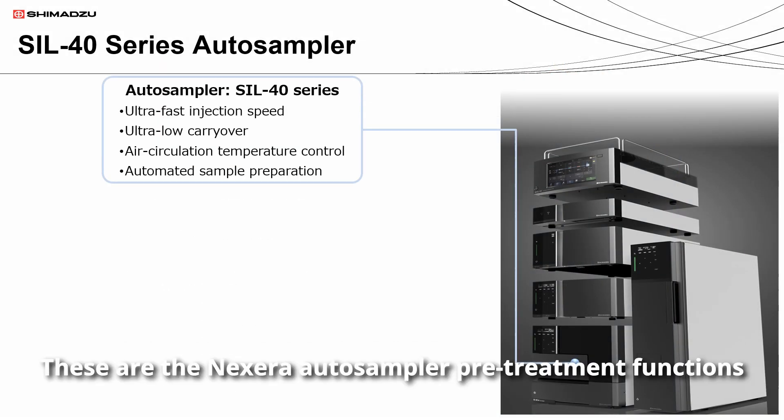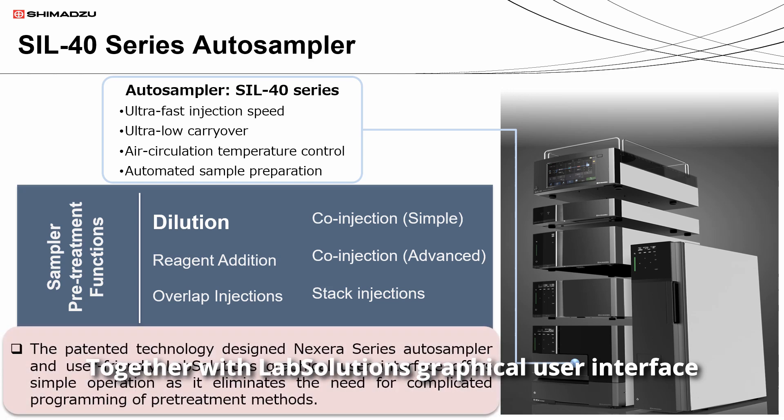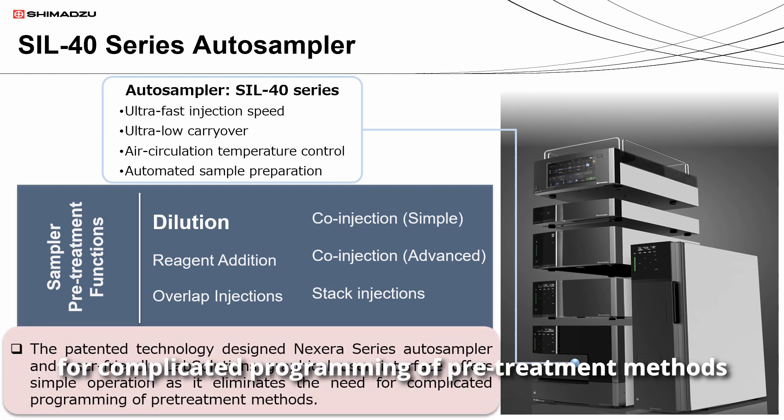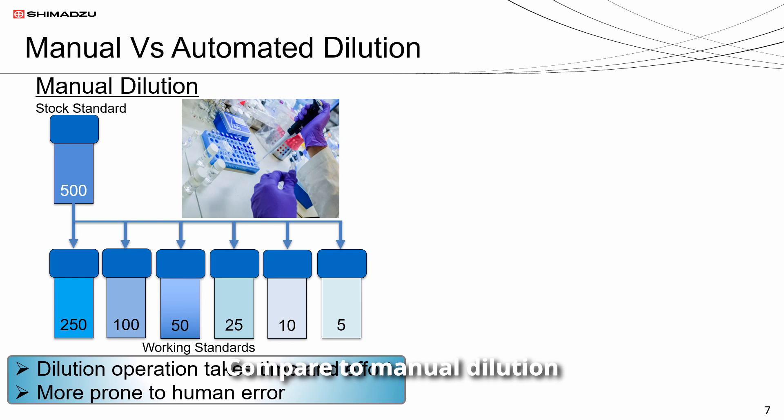These are the Nexera autosampler pre-treatment functions. Together with LabSolutions graphical user interface, it offers simple operation as it eliminates the need for complicated programming of pre-treatment methods. Compared to manual dilution, in auto dilution the stock standard solution is simply placed in the autosampler rack.